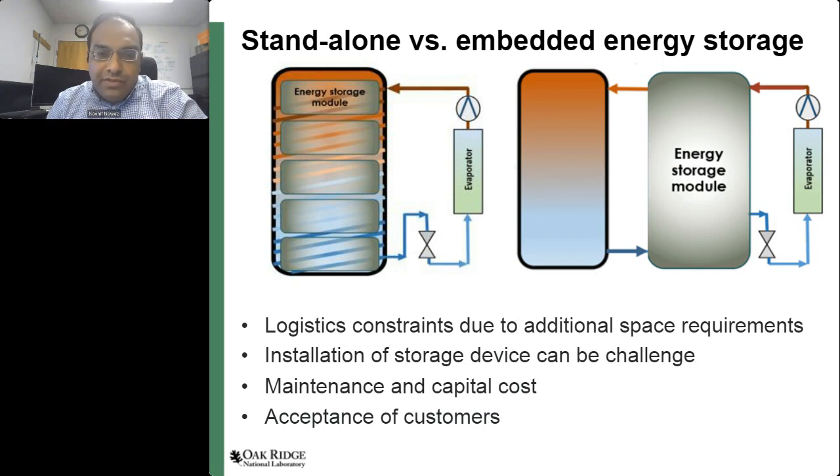Both of these options are functionally great. Again, they can provide us increased capacity. However, if you consider the logistics involved, the option on the left side, which is the embedded energy storage solution, is preferred because, again, I can rely on the OEM to develop a system which will come as a package unit, if you will, and it can be installed without engaging an additional vendor to manufacture or install a dedicated storage device.